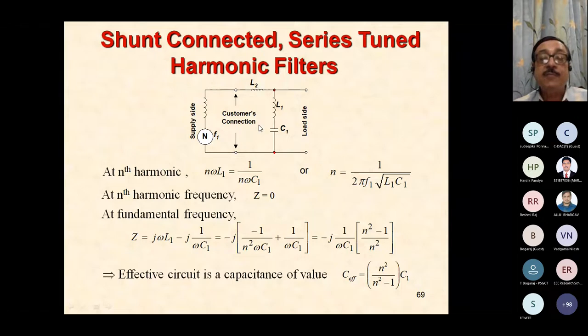Why do we have this L2? It is not a real part of the filter. I have put in this LC tuned filter at my premises such that hardly any harmonic current is getting injected onto the line. But if my next door neighbor has a certain amount of nonlinear loads, then those harmonic currents will have two paths. Path number one is to flow into the supply system with the impedance being n times larger at the nth harmonic, or option number two, in the absence of L2, those currents can flow into my system because this is going to show zero impedance. If those harmonic currents are flowing into my premises, then the metering is again going to show a large content of harmonic current here.